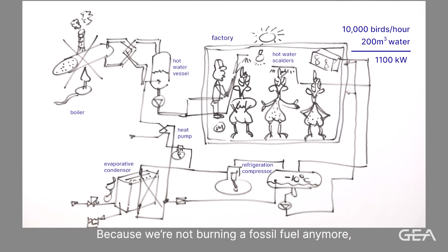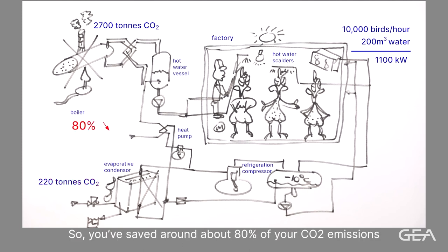But not only that, because we're not burning a fossil fuel anymore, to generate the 1,100 kilowatts would mean we would generate around about 2,700 tons of CO2. Now we're only using 80 kilowatts of electricity through a grid which is becoming ever more green because we've all got wind farms in the countryside generating low-carbon electricity. Then the CO2 emissions go down to about 200, 220 tons of CO2. So you've saved around about 80% of your CO2 emissions simply recovering the heat that you put into the bird in the first place.